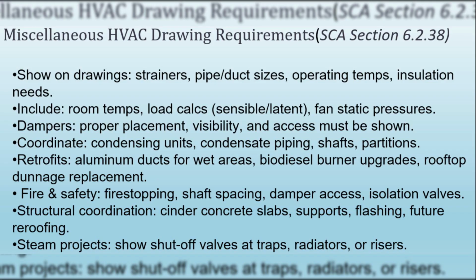Finally, drawings must account for structural realities: cinder concrete slabs, proper supports, shaft extensions, fire stopping, and adequate shaft spacing for duct supports. Designers must also coordinate flashing details with architects, plan for future re-roofing, and ensure shut-off valves for steam radiator traps and risers are shown. In short, this section is about capturing all the small but essential details that prevent problems in construction, code compliance, and future maintenance.